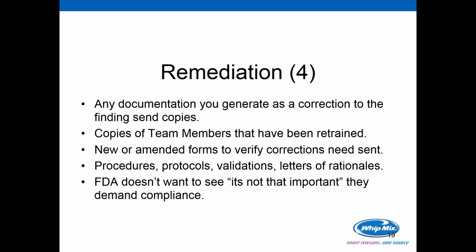And the FDA doesn't want to see "it's not that important." If there is a portion of the regulation that doesn't apply to you, don't say it's not that important. Put information in there that explains perhaps what a requirement is and why your particular operation or your device doesn't need to comply with it. Again, the FDA does not like to see that, which they have seen in the past.